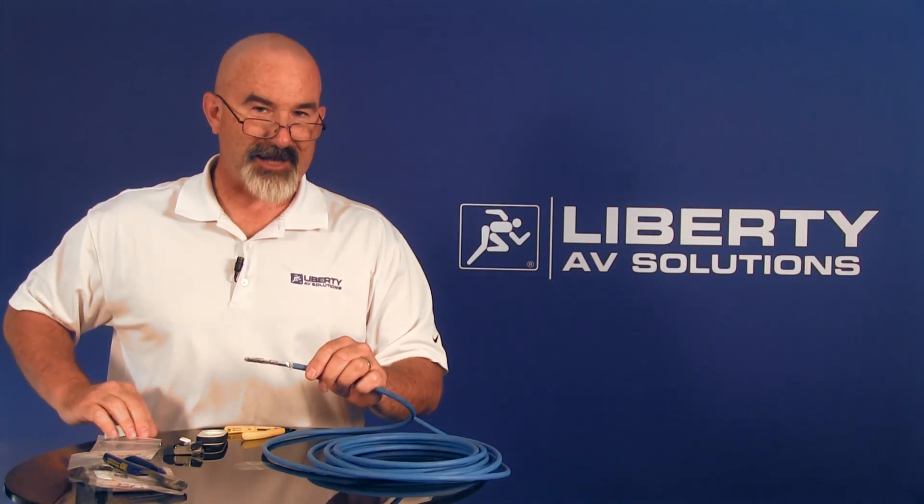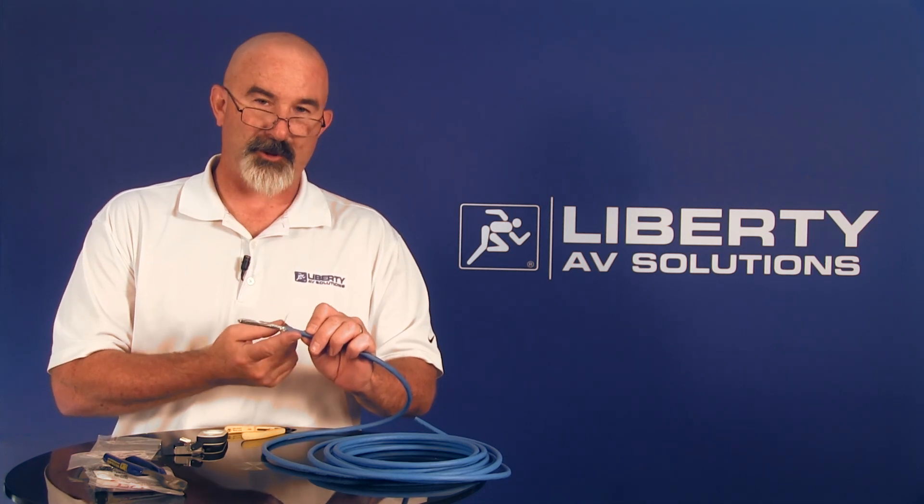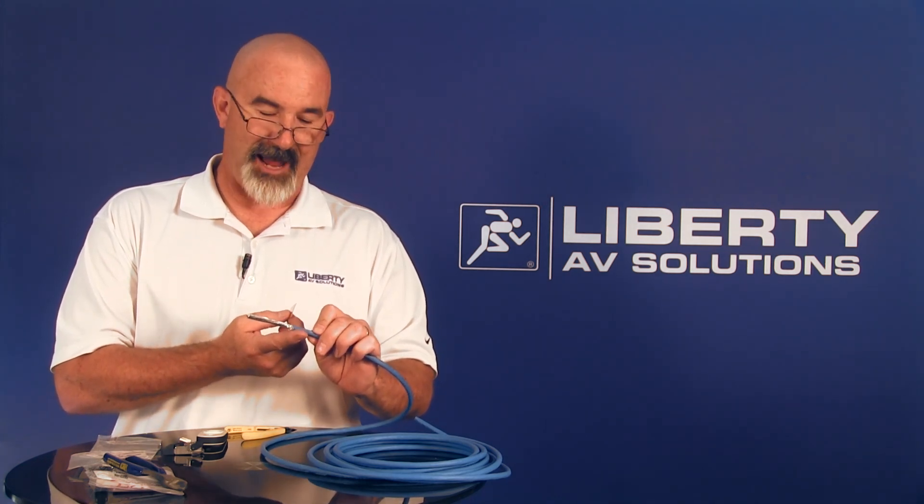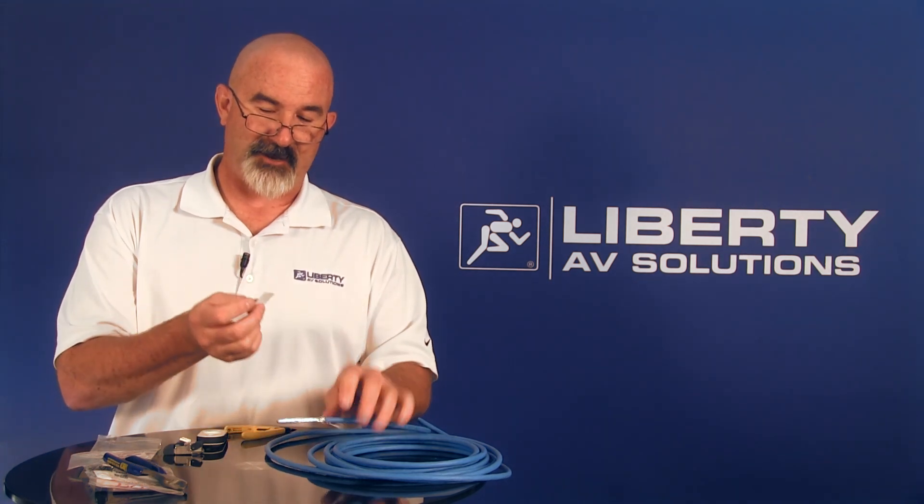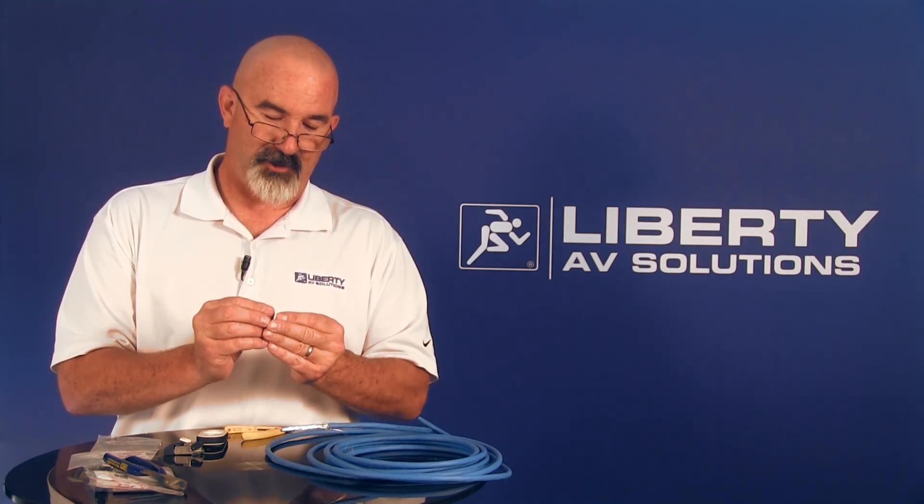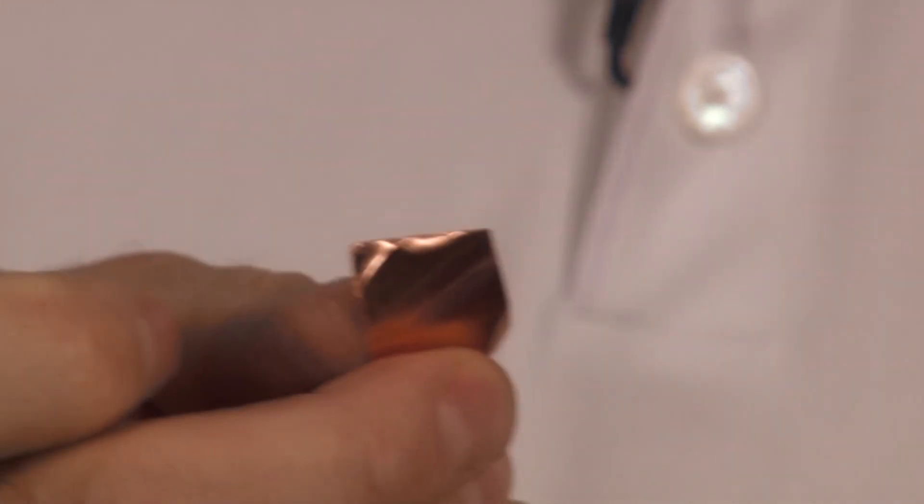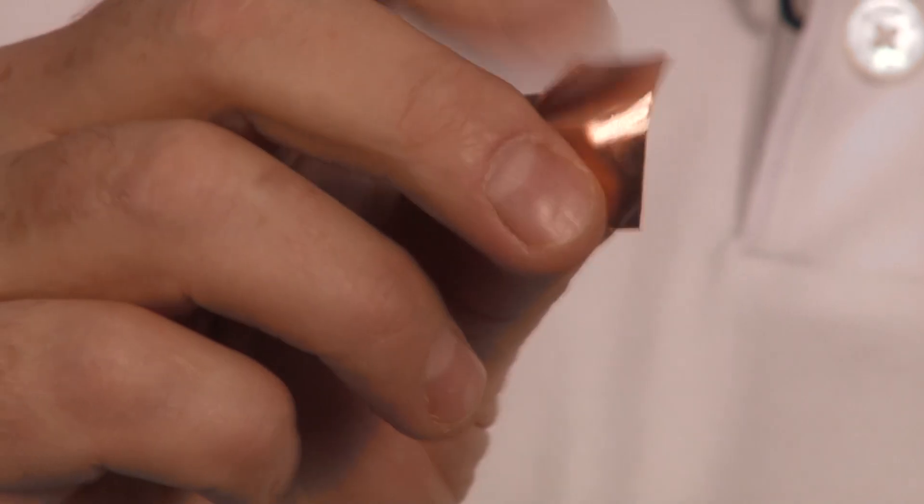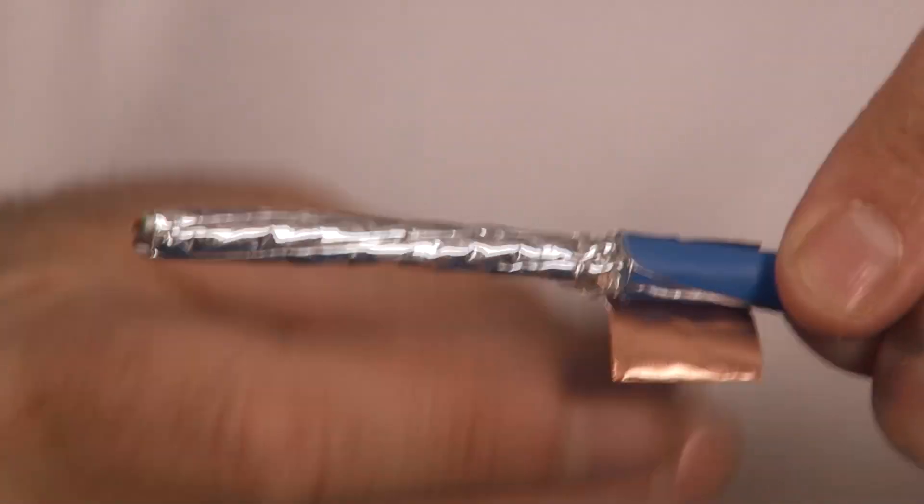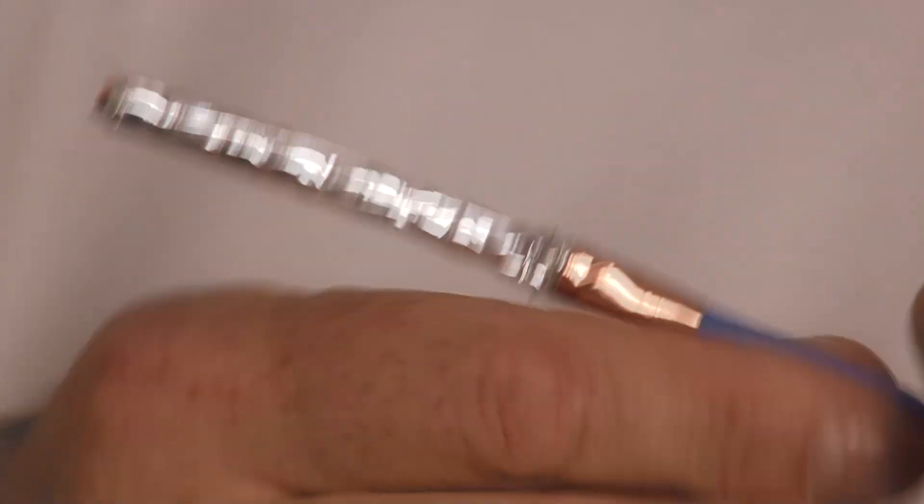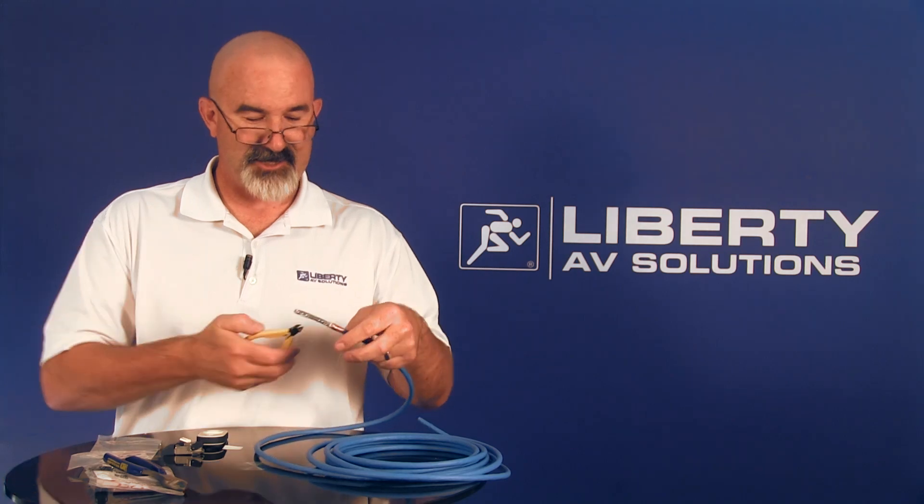Now for best practices with any shielded cable with RJ45 connectors, we recommend putting a little strip of copper tape on the edge of the jacket to capture the drain wire and give you a 360 degree ground. This is 3M 1181 copper tape. It has conductive adhesive. You always want to make sure that whatever copper tape you're using does have conductive adhesive. Now I can trim off my excess on the drain wire.